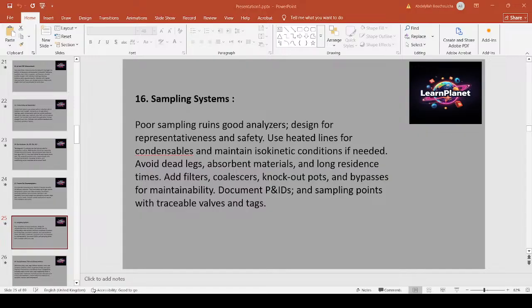A representative sample is the foundation of any analysis. Poor sampling biases all downstream data. Design to avoid dead legs, long residence times, or condensation. Heat and isolate lines for condensable streams, and maintain isokinetic conditions when sampling flowing gas-liquid. Include knockout pots, filters, and bypasses so the analyzer can be serviced without losing samples. Tag and trace sample lines on P&IDs and ensure safe vapor venting arrangements.